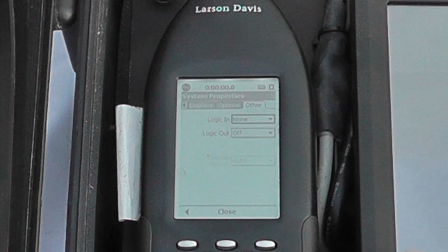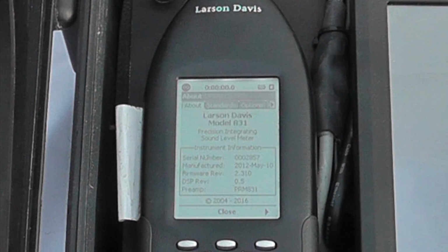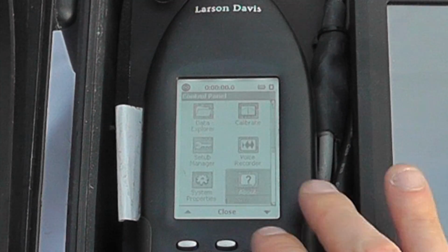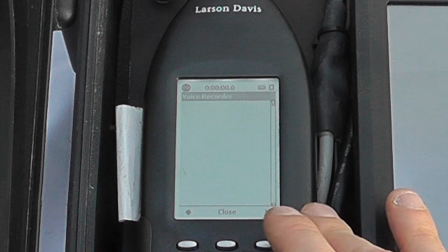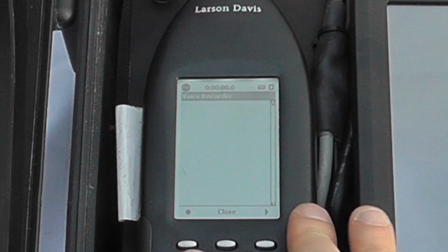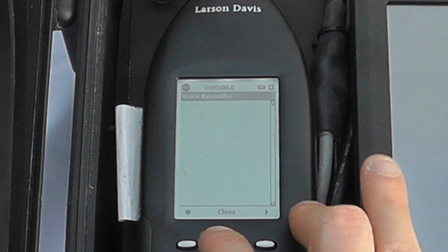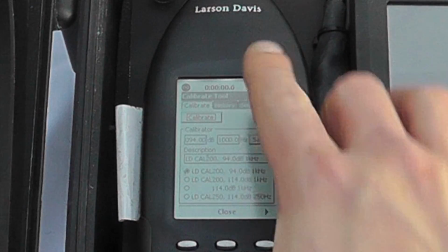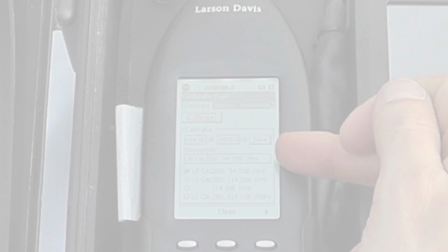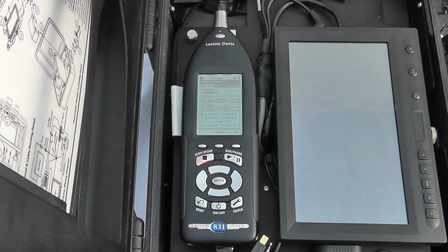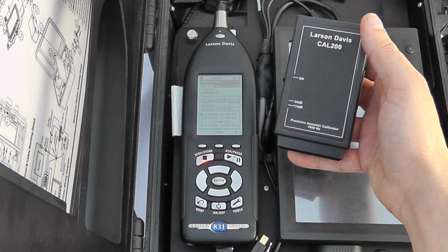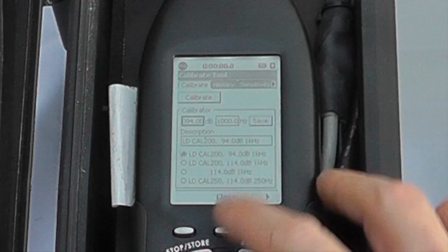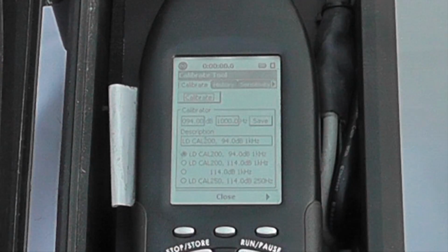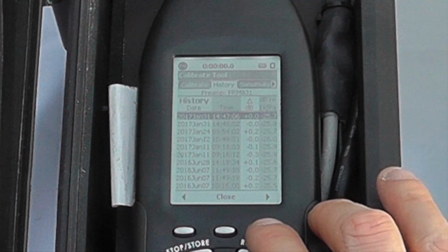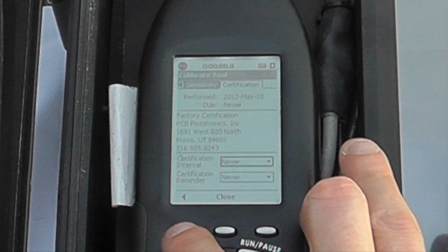So returning to the tools menu, we can see about the device, so how it's set up, any of its firmware history, etc. We can look at any voice, so we can enable voice recording on this particular instrument, so we can record voice annotations if we so wish. We can close the device and then we get into the calibrate function. So we can see what we're calibrating to. So we're calibrating an LD Cal 200, which is the Larson Davis Cal 200 instrument I have here, and we happen to be calibrating at 94 decibels, but we could equally calibrate 114 decibels if we so wish. So to select the calibration, we use the up and down arrows. We can also view any history, any sensitivity data, and a certification.